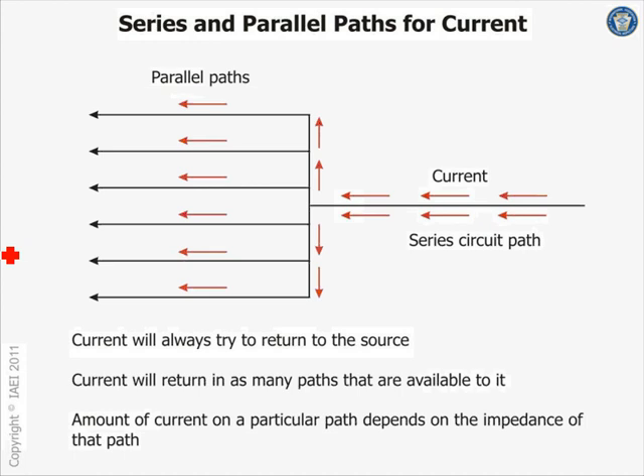Multiple paths. Back to who said that in the agriculture building we used to bond the neutral at multiple buildings in the past. That's why they don't want you to bond the neutral at multiple buildings, because if you're bonding right here at building B and the current is going to building A here, so every coaxial cable, the shield of coaxial cable, every water pipe, every conduit between the two buildings will be carrying current under normal operating condition. Isn't that scary? So you have the coaxial cable going from building A to building B carrying a few amps, taking it back under normal operating condition.